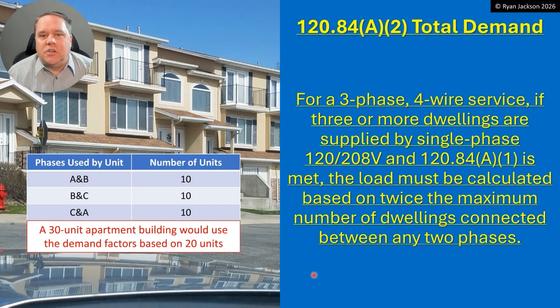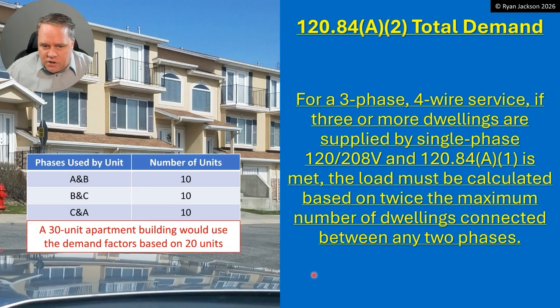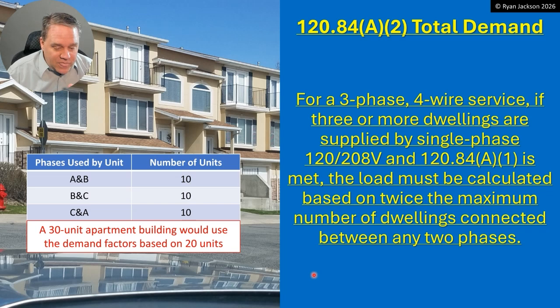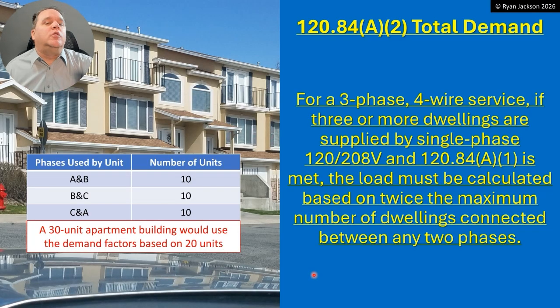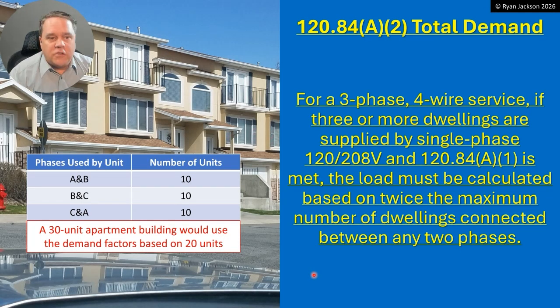So when doing the load calculation — let's say it's 10,000 volt-amps per unit — you're going to say there are only 20 units, not 30. You take 20 units times your calculated load, then plug that into your demand factor. People are misunderstanding this change and saying it screwed them — that now they only get to pretend there are 20 units when doing the demand factor. No. Before you even get to the demand factor, you get to drop 10 units entirely. You look at the 30-unit building and say there are only 20 units here, then multiply by your VA, then apply the demand factor. This will in every instance result in a smaller load calculation than in the 2023 and previous versions.